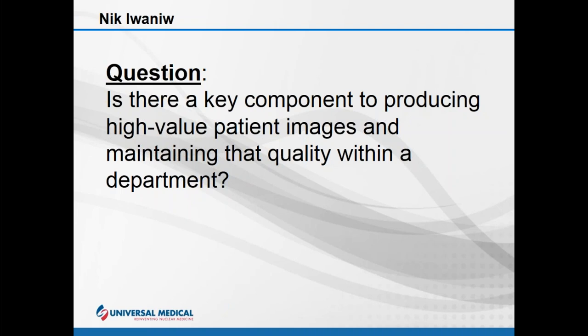So quality images are really important. Some key components from a camera standpoint: it's vitally important that the overall camera operations are performing up to their specification. The mechanical operation is vitally important—positioning, whole body imaging, SPECT imaging, all of those motions calibrated and functioning to their fullest capacity. Is the gantry moving appropriately? These are vitally important, and that calibration is really important in order to create that quality image to make that diagnosis.